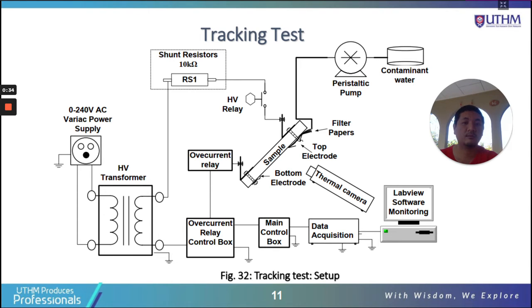All right, place here. And then same thing, we will have an HV transformer to supply the HV AC. You can see here it is connected to the top of the sample, and then the bottom of the sample is connected to the ground. That is basically the main arrangement. We want to test the insulation, so we have to supply high voltage and ground. One side we connect to high voltage, the other side we connect to the ground.